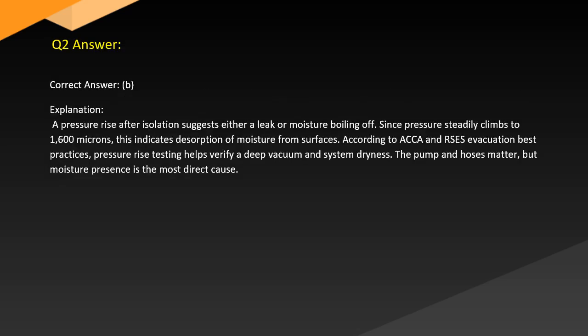Answer. Correct answer, B. Explanation. A pressure rise after isolation suggests either a leak or moisture boiling off. Since pressure steadily climbs to 1600 microns, this indicates desorption of moisture from surfaces. According to ACCA and RSES evacuation best practices, pressure rise testing helps verify a deep vacuum and system dryness. The pump and hoses matter, but moisture presence is the most direct cause.